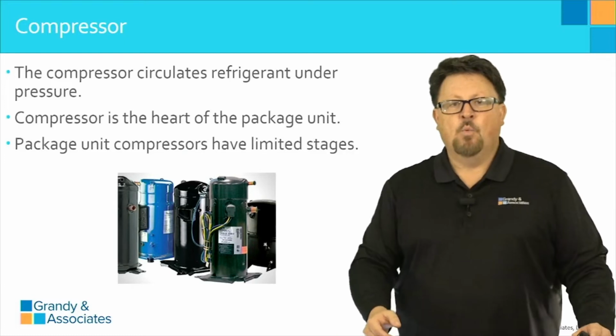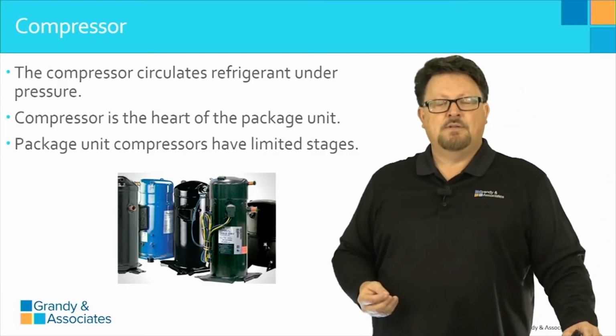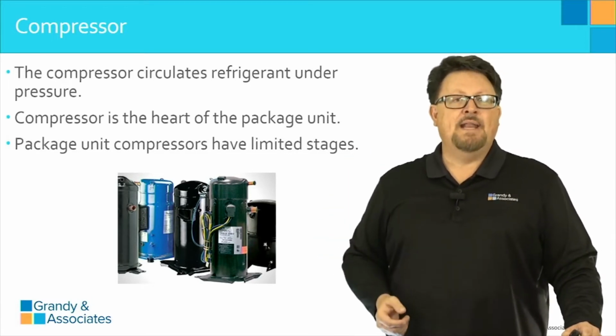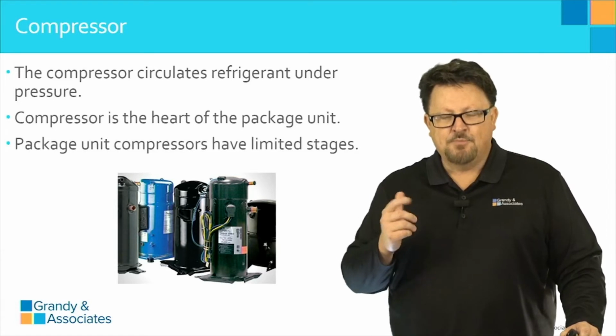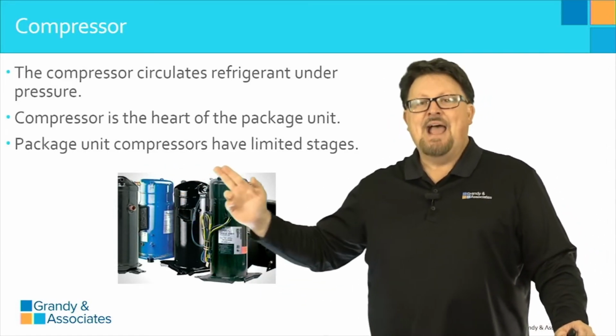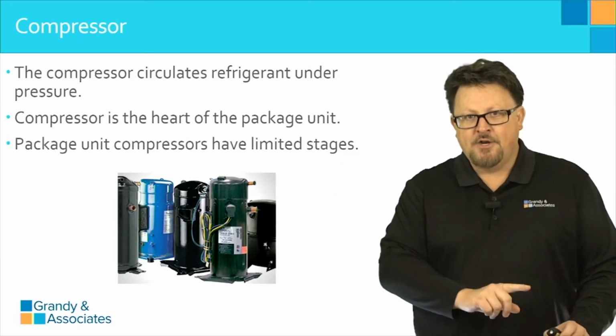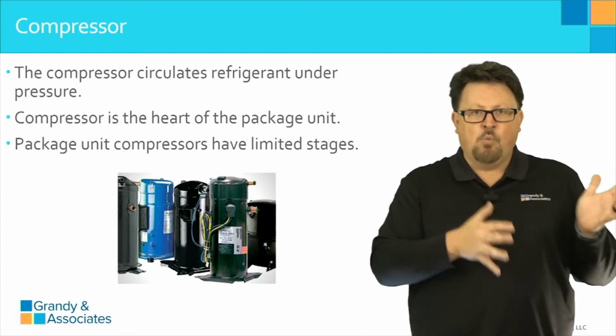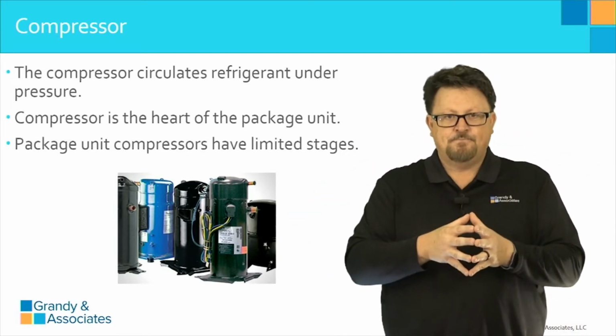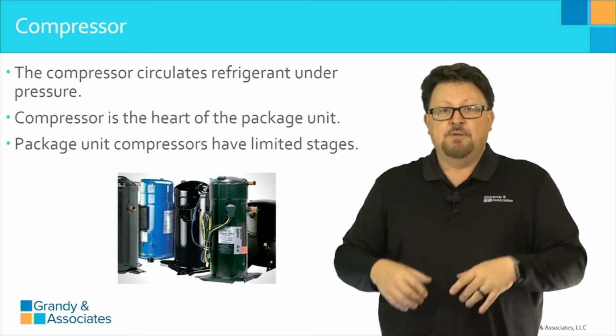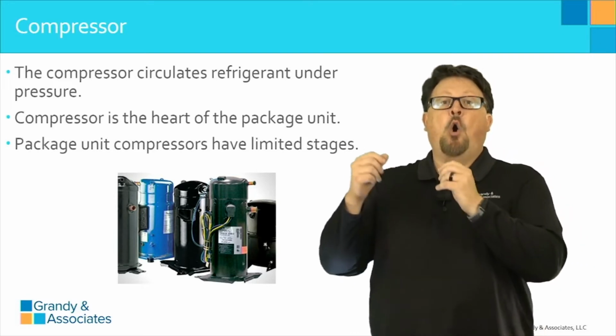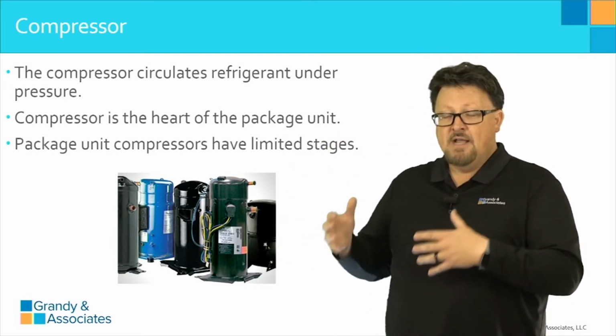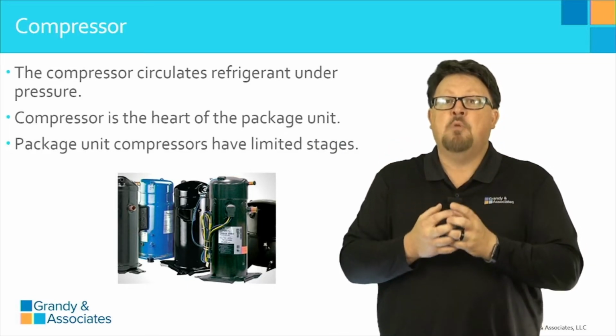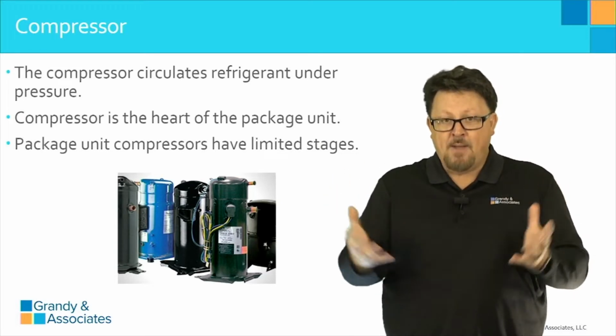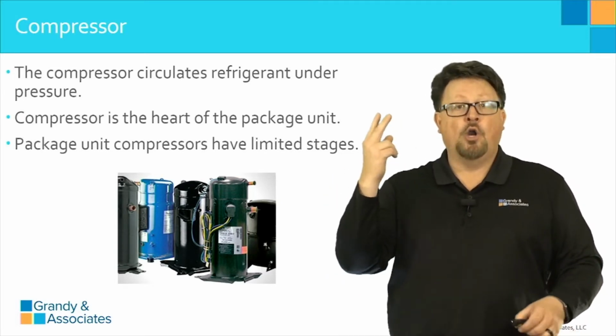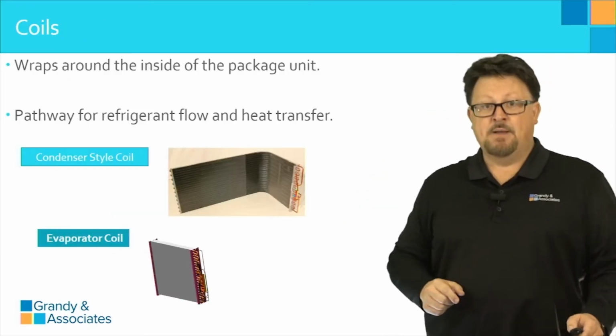The gas package unit will have a compressor. The compressor is the heart of the package unit, circulating refrigerant under pressure. One thing to note: package unit compressors have limited stages. We said earlier, in session number 1 with a split system configuration, that the compressor could be 1 stage, 2 stages, or hundreds of stages. Well, here we discover that with package units, the stages are much more limited. Most of the package units popular in the market today will have 1 stage or 2. That's a worthy distinction to keep in mind.